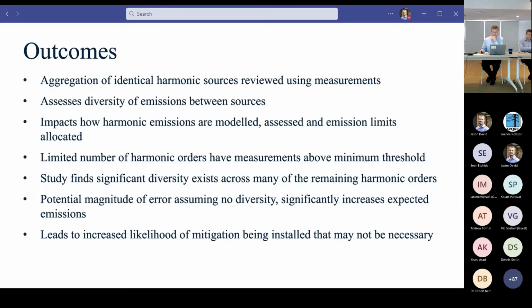So some high-level outcomes. Ultimately, what we're seeing is that there is a significant amount of diversity between identical harmonic sources operating under very similar conditions. We also found that there were a limited number of harmonic orders that actually had measurements above the minimum threshold, making it difficult to determine the degree of diversity, but certainly identifying that diversity did exist.